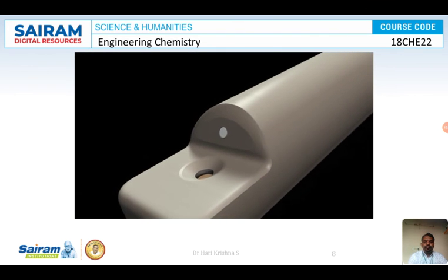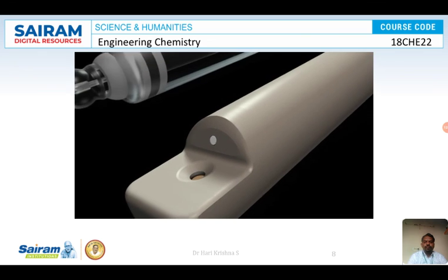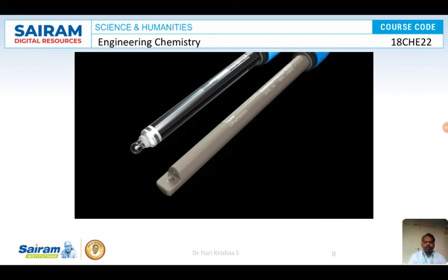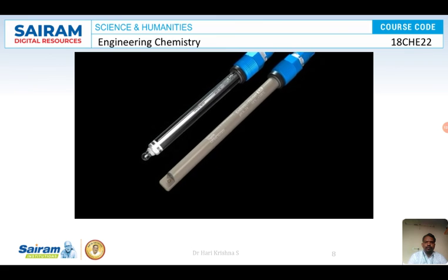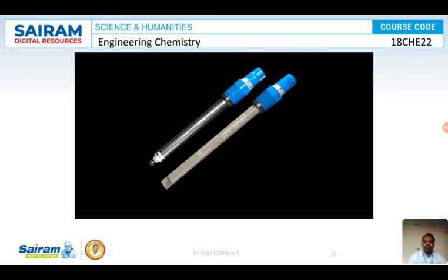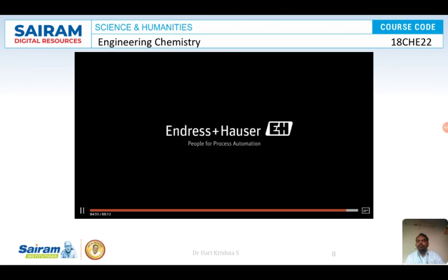Just like the glass sensors, the ISFET sensor also needs a stable reference potential. The potential that forms at the ISFET can then accurately be measured against it. The reference system is also protected from the measured solution by a so-called junction. The potentiometric measuring principle by Endress+Hauser enables highly accurate pH measurement for better product yields and less waste. We offer a solution for all applications, even in those industries that do not tolerate glass. For further information on liquid...